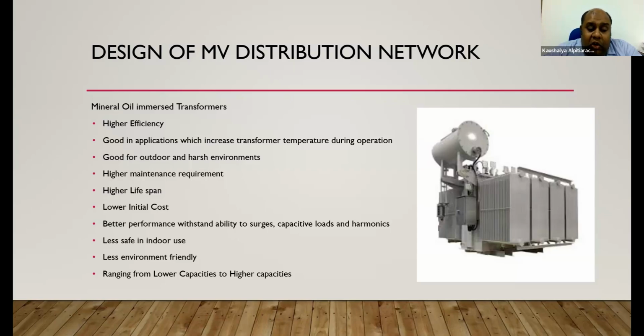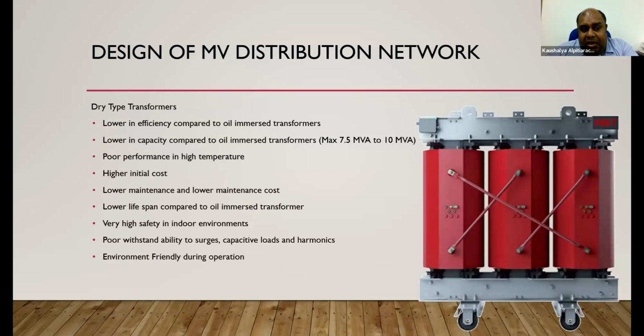higher lifespan, lower initial cost, better performance, withstandability to surge, capacitive loads, and harmonics. Less safer in indoor use, less environmental friendly because of your oil disposals, ranging from lower capacities to very higher capacities. Dry type transformer, lower in efficiency compared to oil immersed transformers, lower in capacity also compared to oil immersed transformers. Max you see somewhere around 7.5 MVA to 10 MVA.